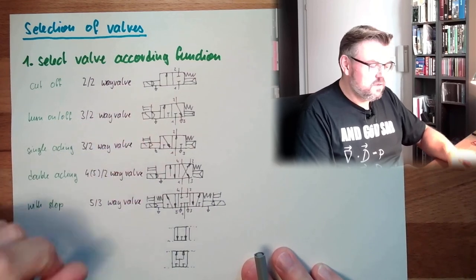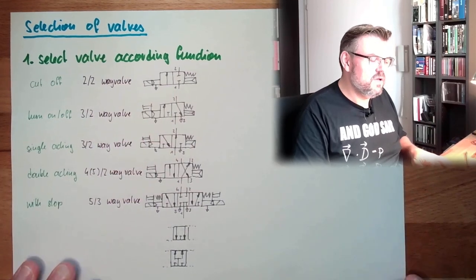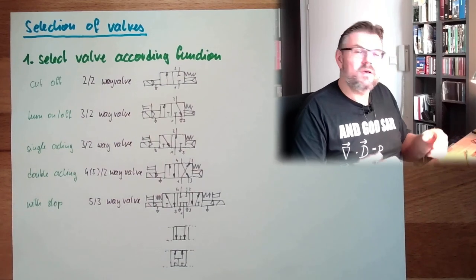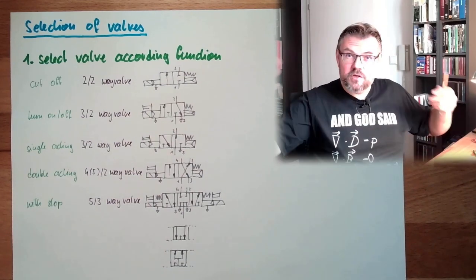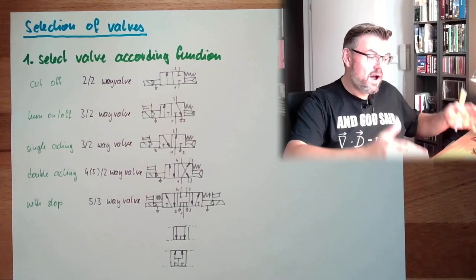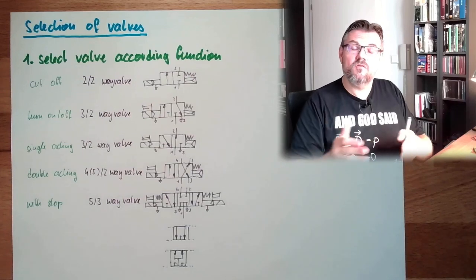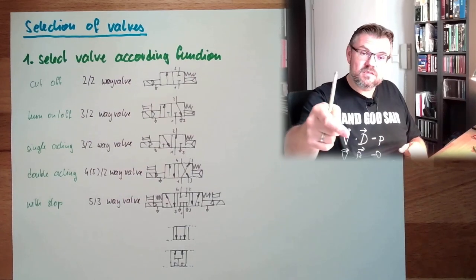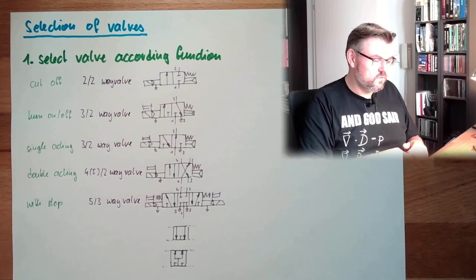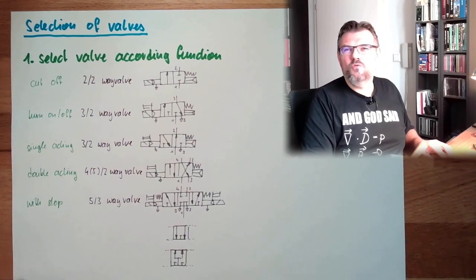I also draw everywhere a hand manual operation. Because this is pretty usual, that we can control the valves manually as well. Because you know, during commissioning, when the control system is not ready yet, not ready wired and so on, and you want to check already the function, it is really nice if you can just press it a little.